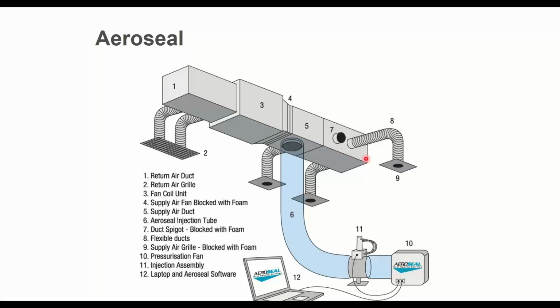this duct. Exact same thing we were doing with that duct leakage test earlier. The only thing that's going to be different, other than the foam blocks versus tape, is that we are going to put in this injection machine here in line with it. This is a wand. It is going to bring in compressed air, and it's going to bring in liquid glue, and it's going to mix those two and create an aerosol for us.